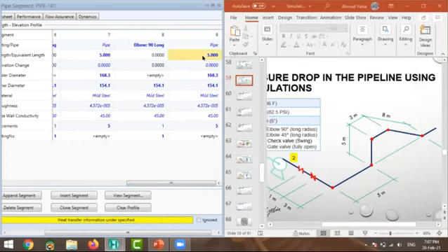But here we have length and we have elevation. We have length 5 meter. Okay, it's typed here. And we have elevation change. The elevation change here is positive five, because the pipe here is going up, or the fluid direction is going up. Okay, I will add the elbow here. It's 90 degree also, cloned from this elbow.